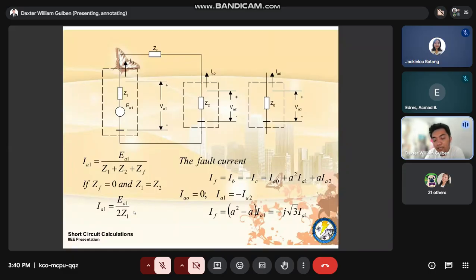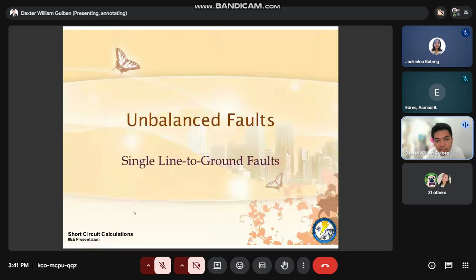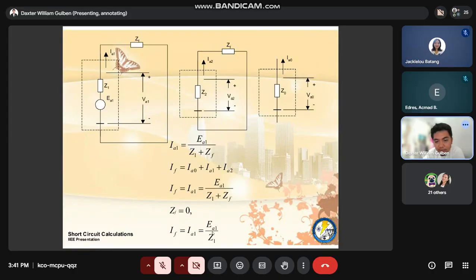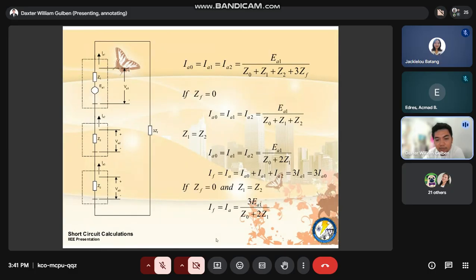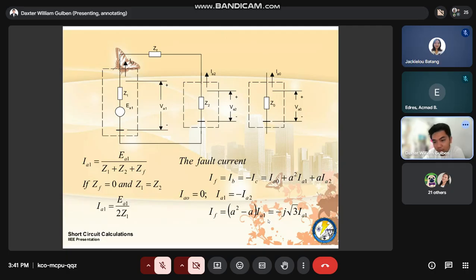Okay? So, I hope kini nga mga formula sa fault currents, atong dumduman, no? Mao usually ang gina-ask sa board exam. How do you compute the line-to-line fault if you're given this? So, kana gyud atong dumduman. Kung i-recall, no, sa three-phase, pre-fault voltage divided by Z1. Sa single line to ground, 3 times the pre-fault voltage divided by Z0 plus 2Z1. Sa line to line, you have negative j square root of 3 times the EA1 divided by 2Z1.